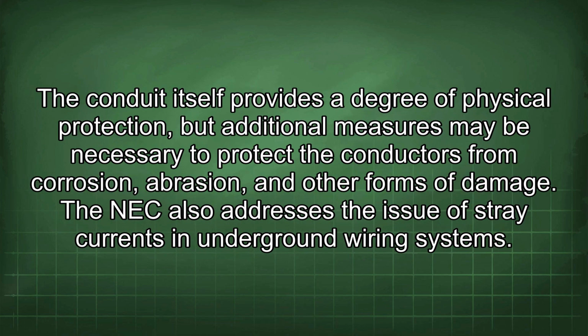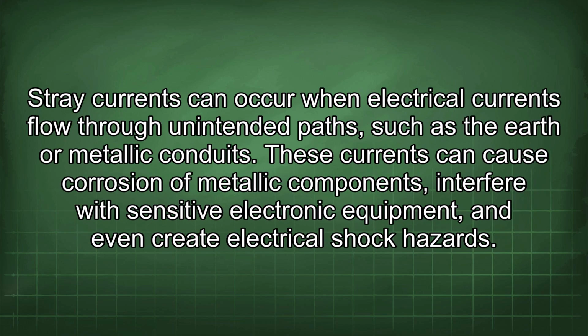The conduit itself provides a degree of physical protection, but additional measures may be necessary to protect the conductors from corrosion, abrasion, and other forms of damage. The NEC also addresses the issue of stray currents in underground wiring systems. Stray currents can occur when electrical currents flow through unintended paths such as the earth or metallic conduits. These currents can cause corrosion of metallic components, interfere with sensitive electronic equipment, and even create electrical shock hazards.